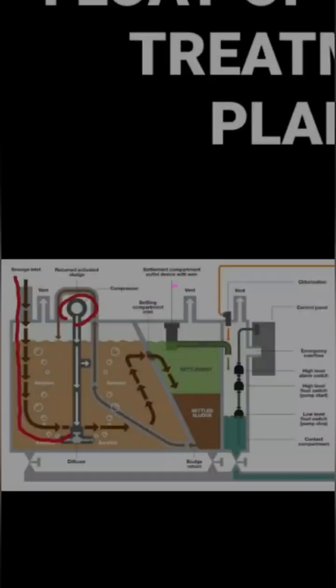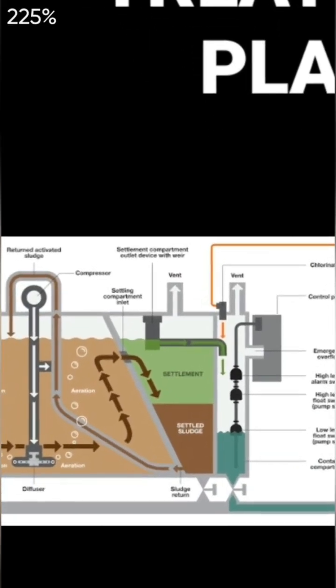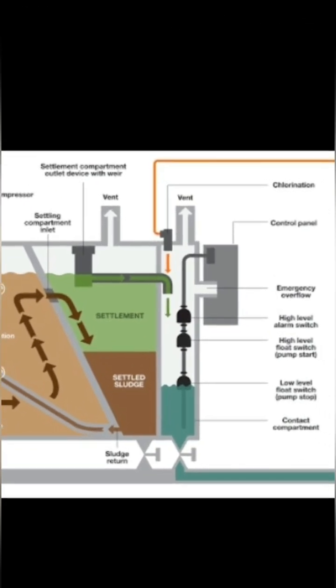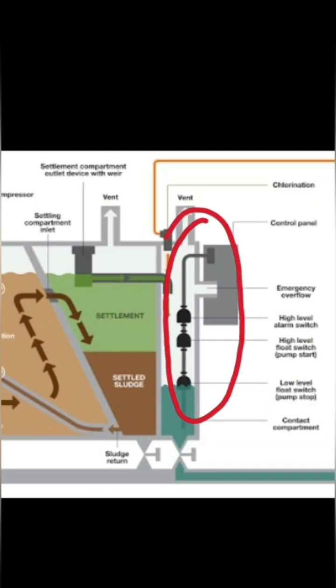This is the basic concept. Afterwards, as you can see, the final chamber is the chlorination chamber, where the clean water gets filled up. Here we have the float switch. You can see the float switch has three floats: the high level alarm switch on the top, the low level switch on the bottom, and in between is the high level switch. The low level is for stopping the pump.